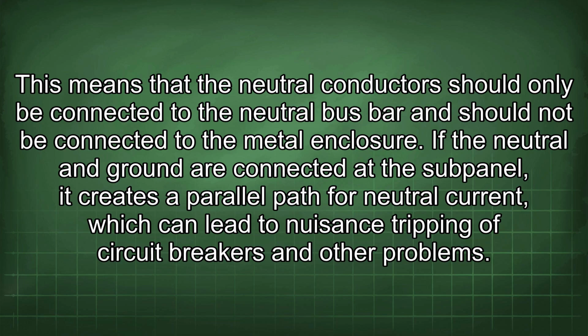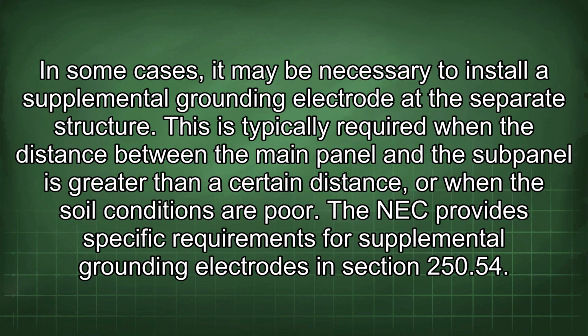If the neutral and ground are connected at the subpanel, it creates a parallel path for neutral current, which can lead to nuisance tripping of circuit breakers and other problems. In some cases, it may be necessary to install a supplemental grounding electrode at the separate structure. This is typically required when the distance between the main panel and the subpanel is greater than a certain distance, or when the soil conditions are poor.